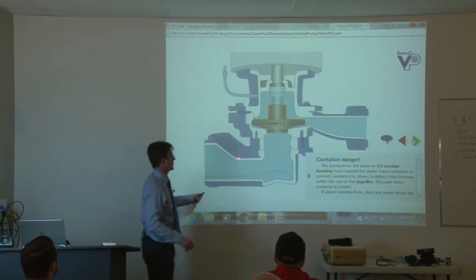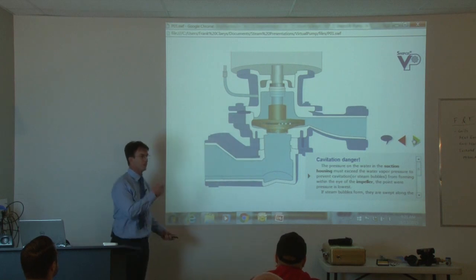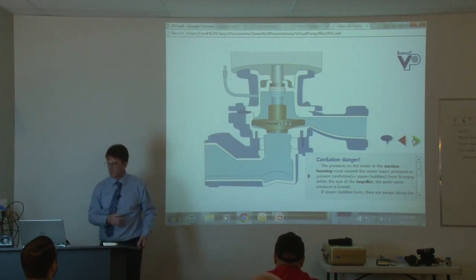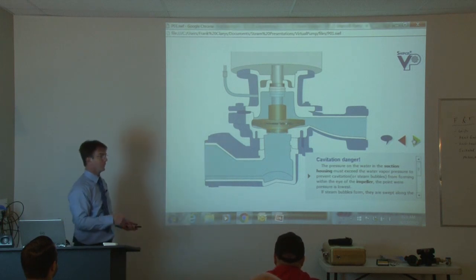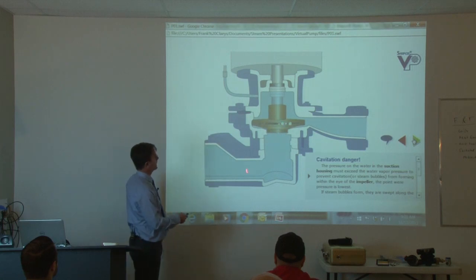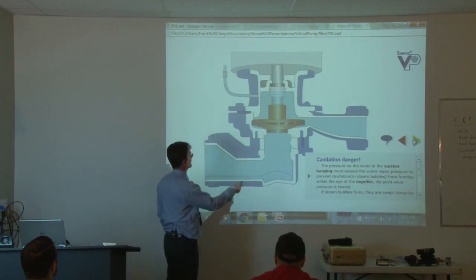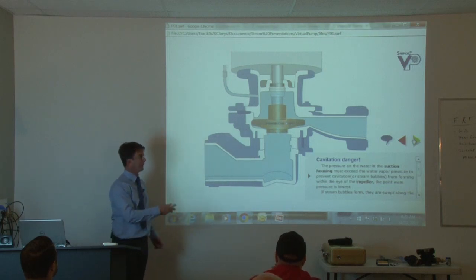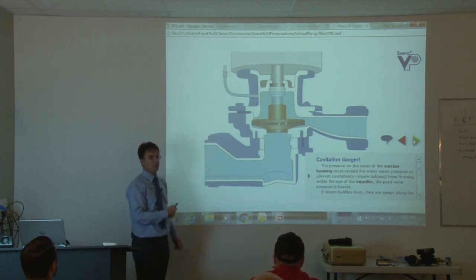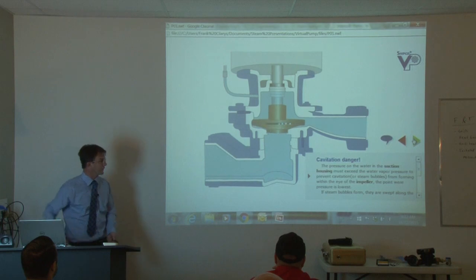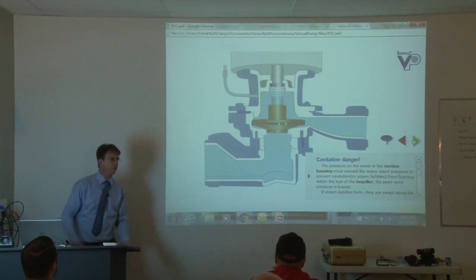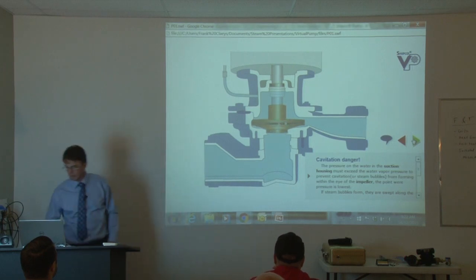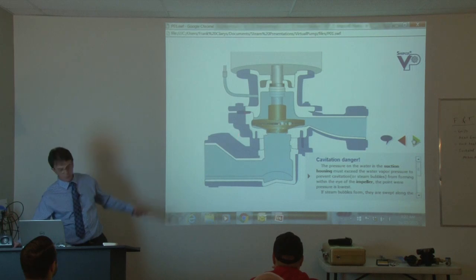Cavitation danger: cavitation can happen if you have many leaking steam traps or if steam enters the pump housing. If air gets into your pump - or if the water temperature coming in is too high - it can turn back into steam and cause cavitation. Cavitation sounds like somebody shoveling rocks into your pump - a really grinding, annoying sound. Cavitation is not good: it will damage your pump very quickly and will damage the motor as well.